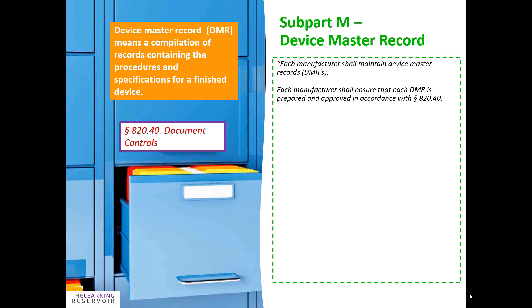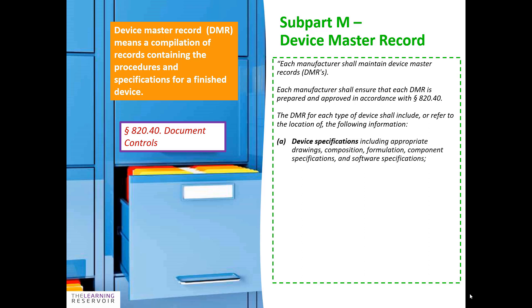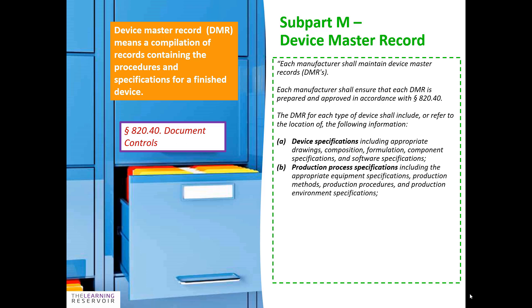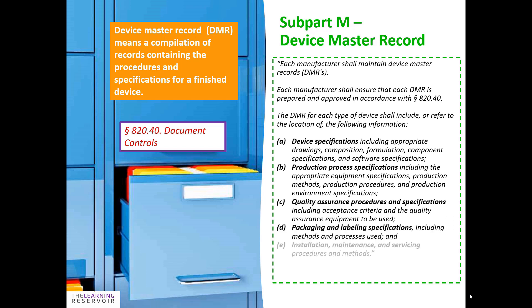§820.40 is our document controls requirement in 21 CFR Part 820. What it's saying is that they want you to have your device master records containing procedures and specifications that relate to the finished device, and those procedures and specifications must be written in accordance with the requirements within §820.40. The DMR for each type of device should include or refer to the location of device specifications, production process specifications, quality assurance procedures and specifications, packaging and labeling specifications, and installation, maintenance, and servicing specifications. All those procedures and specifications that relate to the finished device form your device master record, and a medical device manufacturing facility has to have that in place.